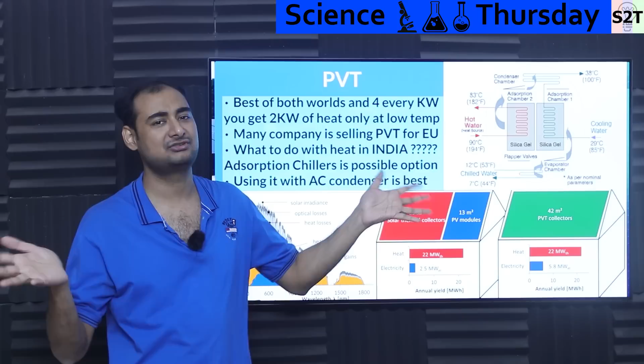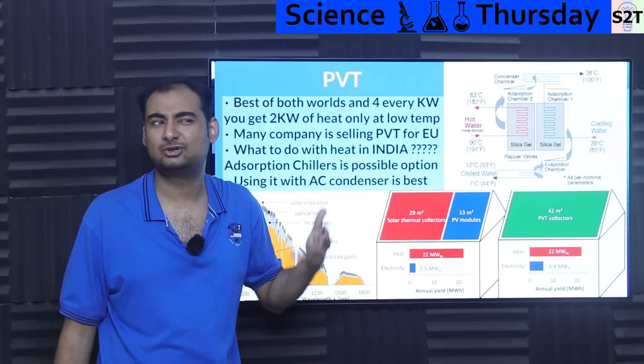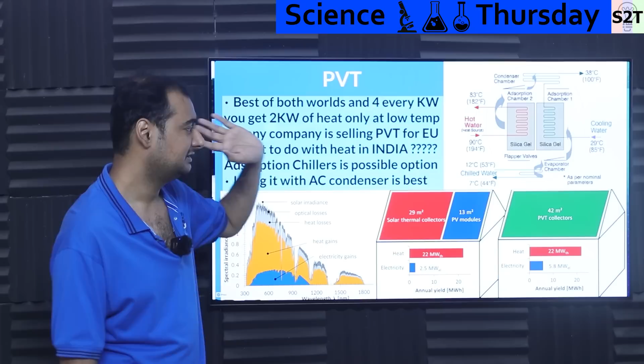There are two places where it can have an effect. First, the coefficient of performance drops, but we have so much waste heat that it typically doesn't matter. Second, chilled water temperature will go up, but we don't need cold water as long as we can have human body temperature water, meaning 20 degrees Celsius water is good enough. We do not need 7 degrees Celsius.